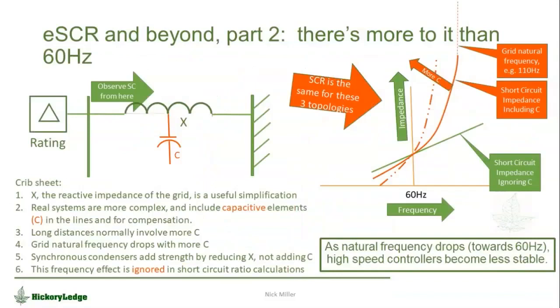So now that's one aspect. This next slide is another relatively poorly understood, or at least not widely understood, phenomenon. And that is that the power system, you know, we worry about impedance. We think in terms of 60 hertz fundamental frequency, but the power system isn't made of X's. It's made of impedances and capacitance and other things, which means that its impedance changes with frequency. All right, very basic power system engineering. But if we only talk about the X in short circuit ratio, you get on the right-hand side an impedance that changes linearly with frequency. That's the green line on my chart on the right.